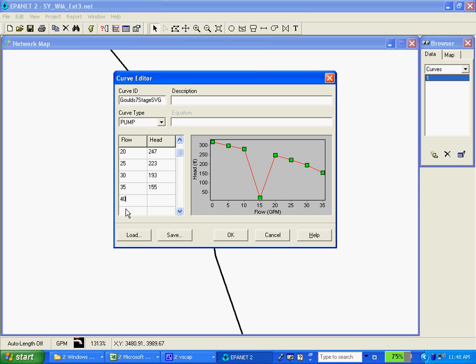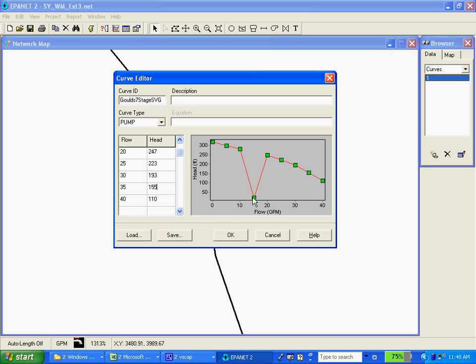My last point here is 40. My booster station is a very small booster station. Pretty small pump in there. See there, we've got an error somewhere, obviously somewhere at the 15 mark. We've now entered a strange number, so we're getting this dip in the curve. It's kind of nice to have this graph to be able to see that, otherwise you might miss it.